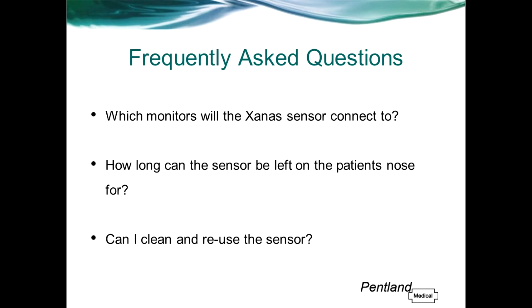Which monitors will the Xanas sensor connect to? The Xanas sensor will connect to any monitors which are compatible with Nellcor sensors. This includes Philips monitors providing you have the relevant interface cable. As a general rule, we can't connect directly to any Masimo equipment, although in some cases there are cables available which will allow compatibility.